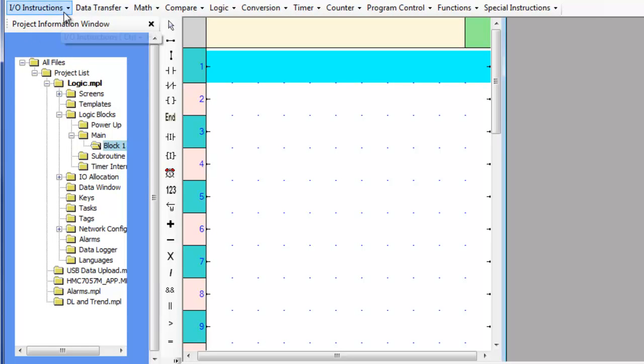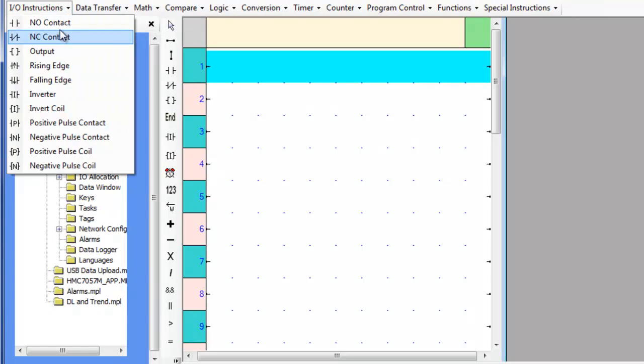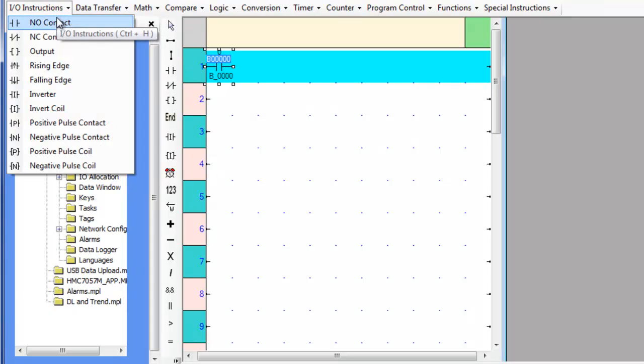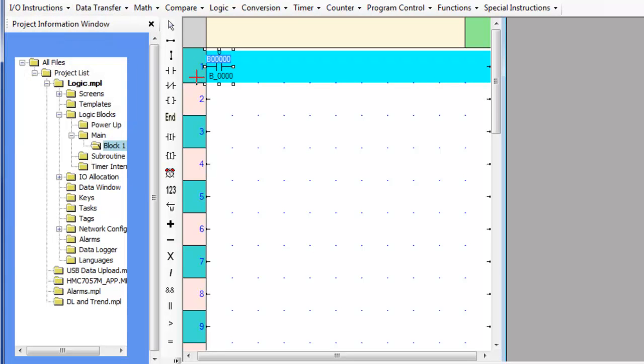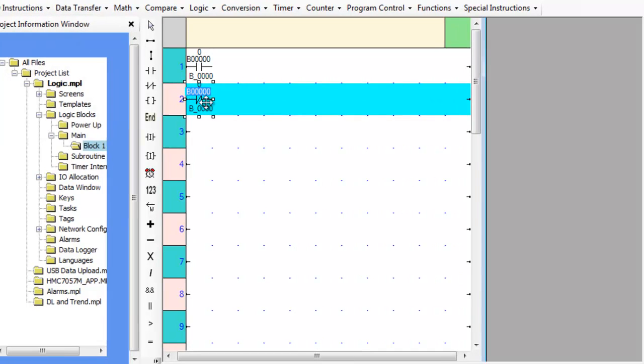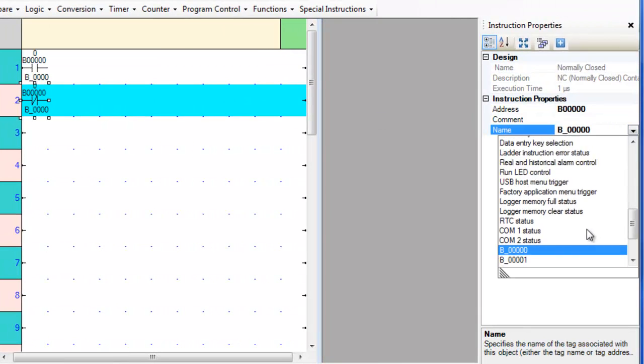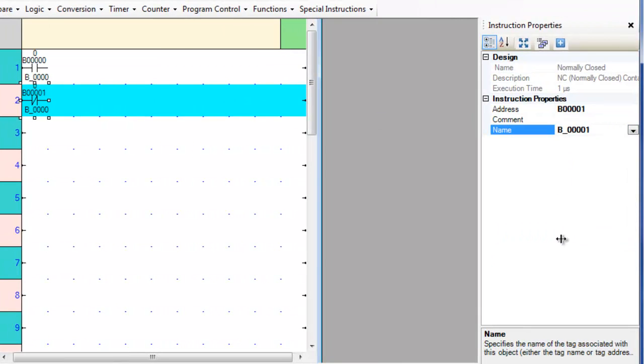The normally open contact is a logic condition that will be true when the associated bit is set. The normally closed contact is a logic condition that will be true when the associated bit is clear. The execution time of these instructions is one microsecond.